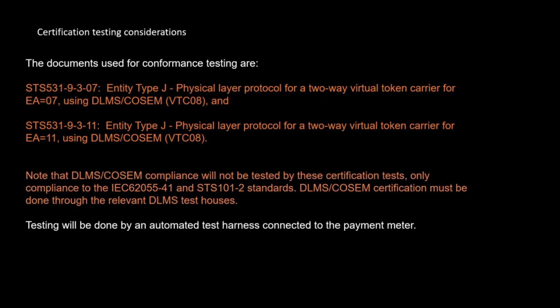Note that DLMS COSEM compliance will not be tested by these certification tests, only compliance to the IEC 62055-41 and STS101-2 standards. DLMS COSEM certification must be done through the relevant DLMS test houses. Testing will be done by an automated test harness connected to the payment meter.